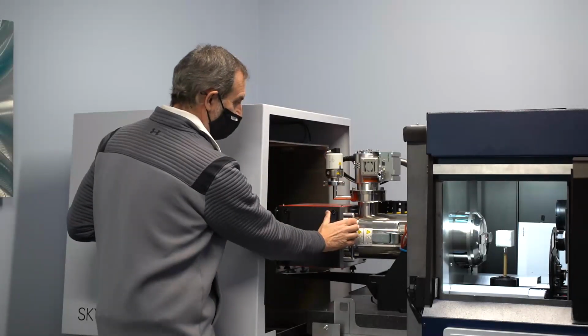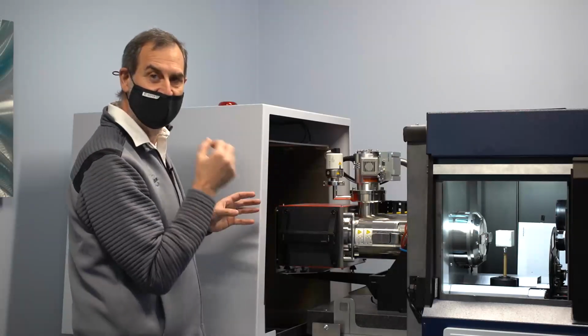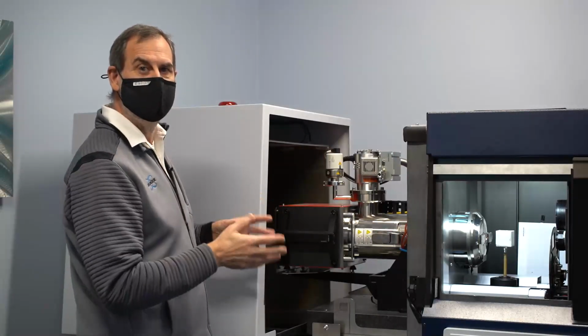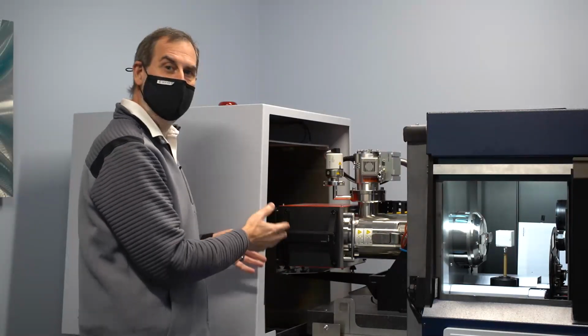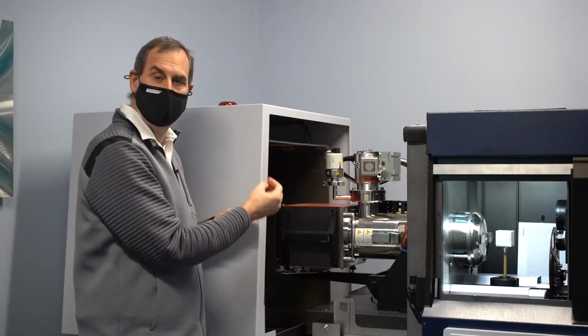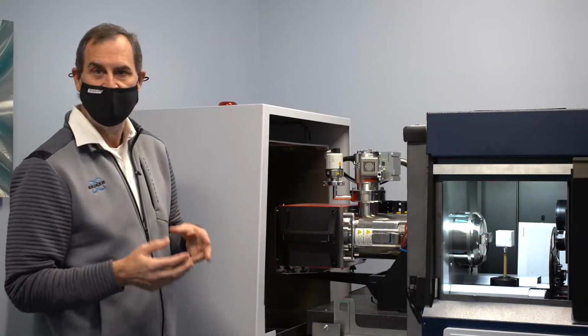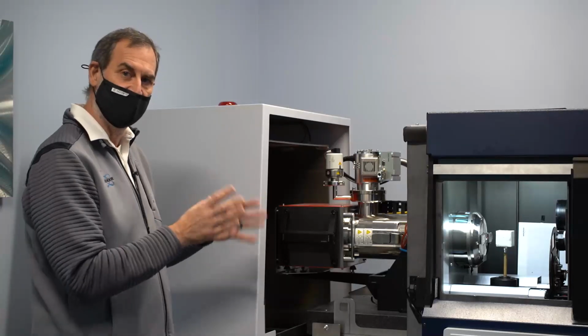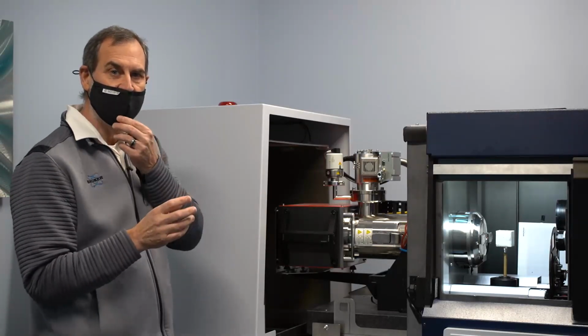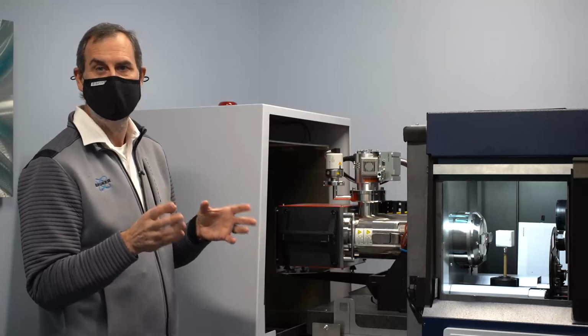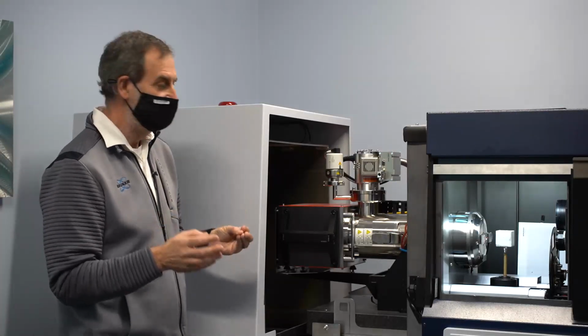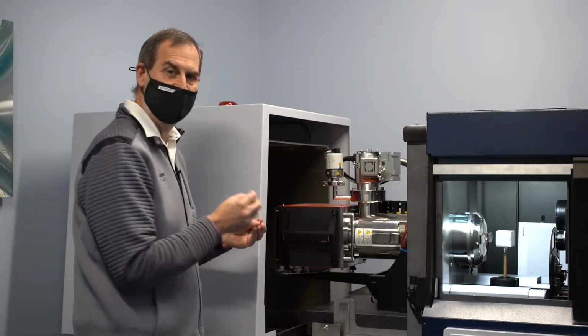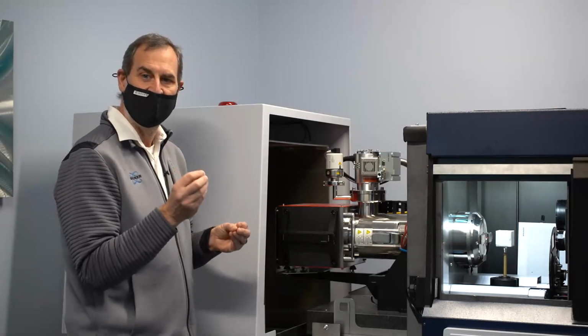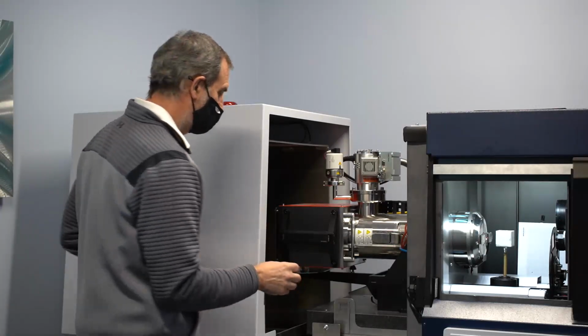Now let's get back to the source. This is a very large high-tech source, but it's also very simple and easy to use. It is an open source, which means it does have filaments, and we provide you with 2 different types of filaments. You have a tungsten filament, and the tungsten is good for high voltages when you really need that power to get through a sample. But it also has a LaB6, and the LaB6 gives you the highest resolution possible.